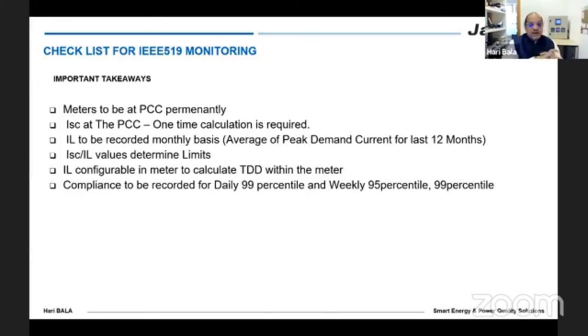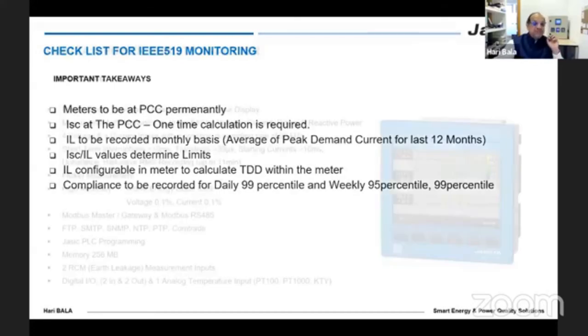The compliance should be recorded for daily 99 percentile, weekly 99 percentile, and 95 percentile, preferably on the meters. Because generally, if you do it outside the meter, you always have the liberty to play around with some data. So it's better that it is done on the meter itself.